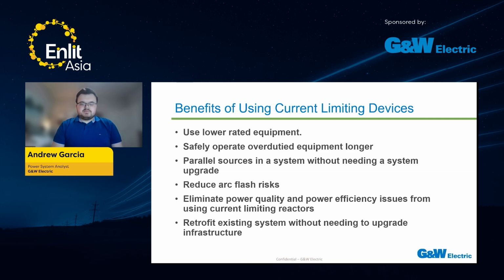And ultimately, one of the better features of this too is if you're looking at a project at an older facility with much higher fault current than it was initially designed for, you can then retrofit that existing system without needing to upgrade your infrastructure. It's all in the same room on the same paths. We do have a question. Question 1: notice that the fault energy is contained in the blue cylinders, what is the action to the fault energy after that? That's a great question.